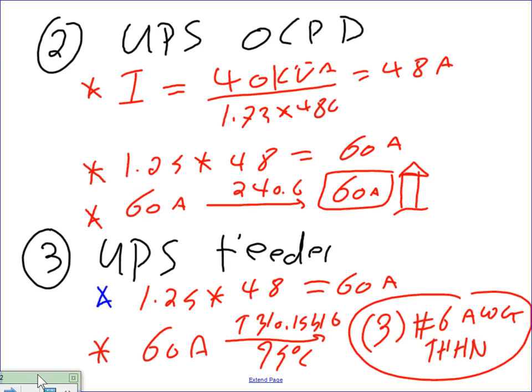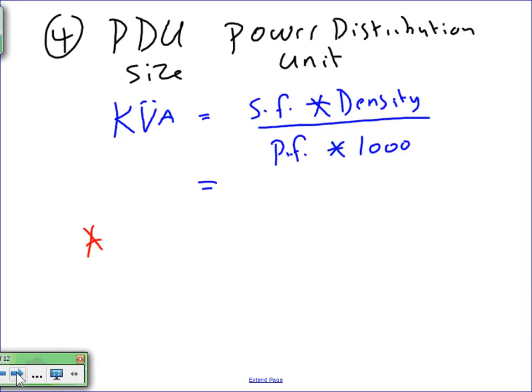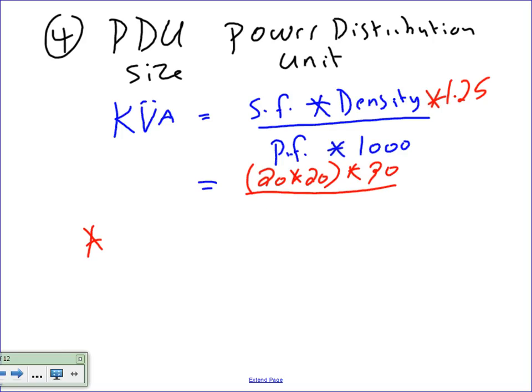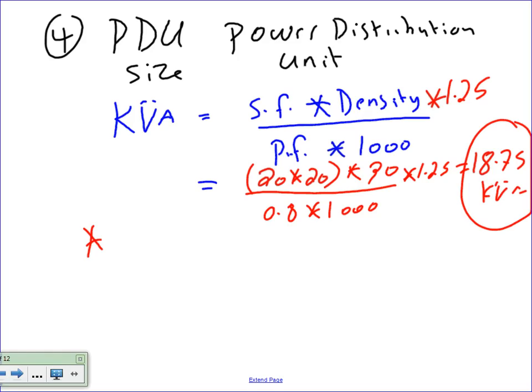Okay, so let's go forward to PDUs. Now we're going to go to the PDU, power distribution units. We're going to size the power distribution unit. Chris, we're going to do it the same way. Please multiply this by 1.25 for losses, continuous load, and so forth. We're going to basically repeat the same process here for the PDUs. It's 20 times 20 for the PDU times 30 divided by 0.8 times 1,000 to make a kVA, multiplied by 1.25. And what did we come up with, Chris? 18.75 kVA. The same size as we did for the UPS.